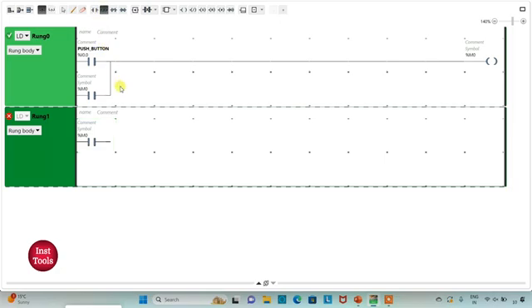To summarize the full logic: when the push button is pressed M0 turns on, and when released M1 becomes true and remains true. When M1 is true the cutting process starts and runs for 10 seconds then stops. When the push button is pressed a second time M2 becomes true, and when released M3 becomes true. When M3 becomes true the polishing process starts and runs for 50 seconds then stops.